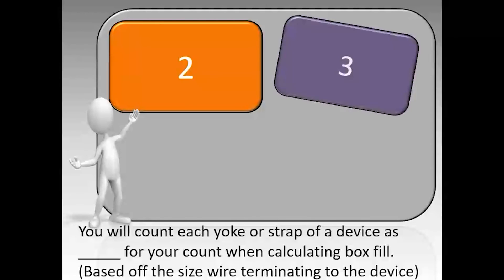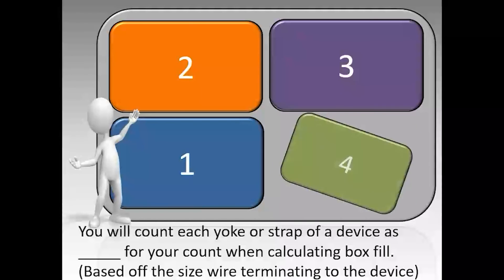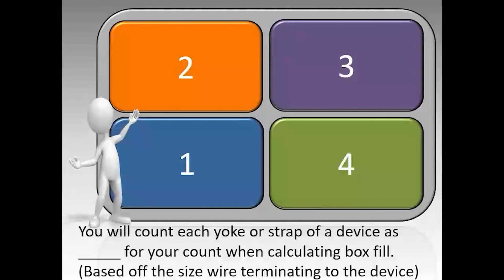You will count each yoke or strap of a device as two conductors for your count when calculating box fill, and this is based off the largest size wire terminating to the device. So if you have a switch with 12-gauge wire, it counts as a number 12. If in the same box you have a switch with 14-gauge wire, that switch would count as 14s and the first switch as 12s. Each yoke or strap counts as two based off the size wire terminating to the device.